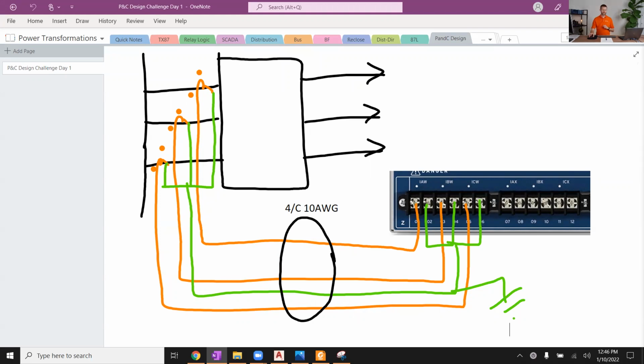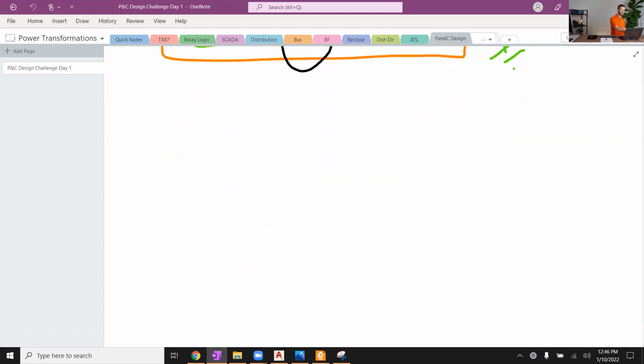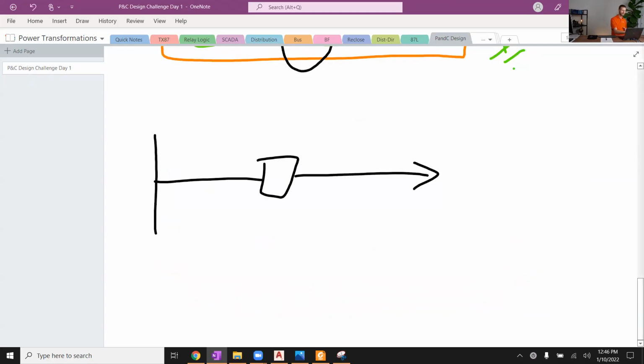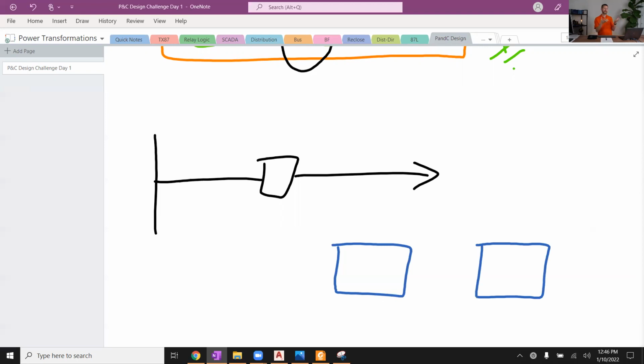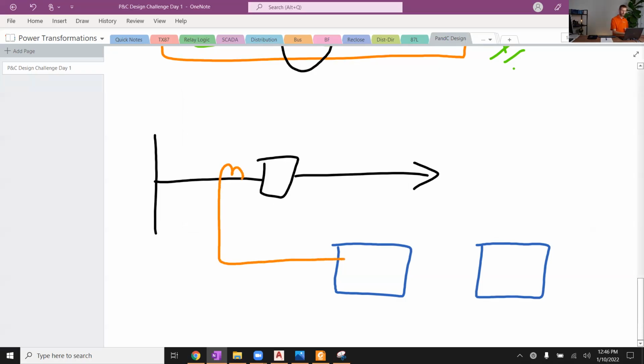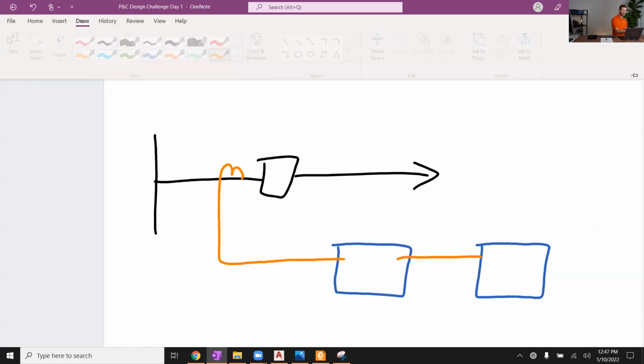What about if you have multiple relays that need the same CTs to be shared? I'm going to do a one-line rendition of this for keeping it simpler. But sometimes you have a breaker and a relay. Let's draw 2 relays this time though. Relay 1 and relay 2. And suppose you did not have 2 sets of CTs, so you could do one set of CTs to one relay and the other set of CTs to the other relay. Suppose you only had one CT available. You needed to share that CT set for both of these relays. In that case, you would have your CT here coming into relay 1. It would come out of relay 1 and go to relay 2. And then from relay 2, I'm going to go to my green color for neutral.